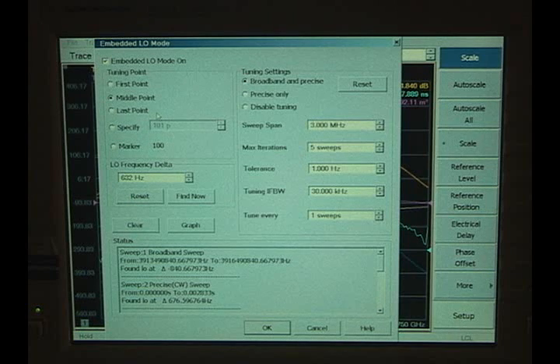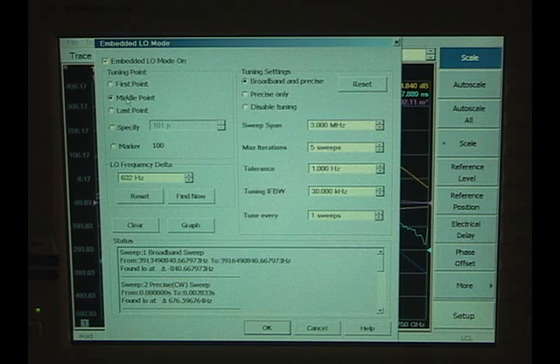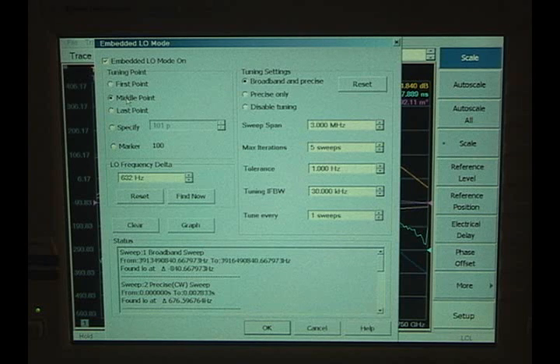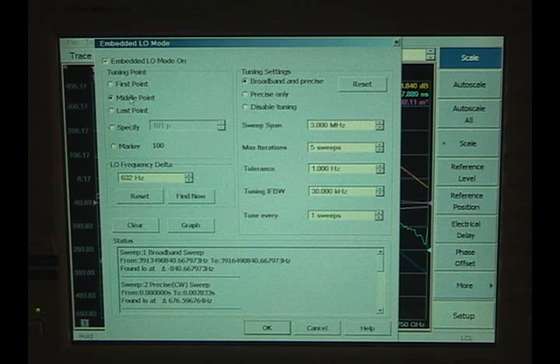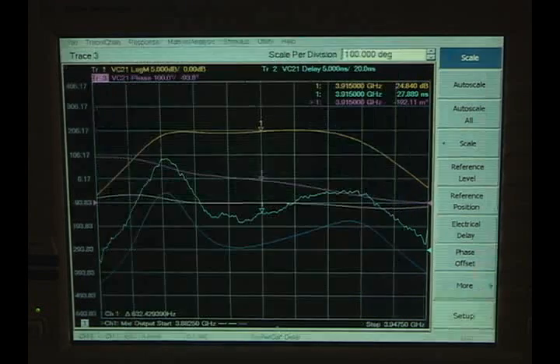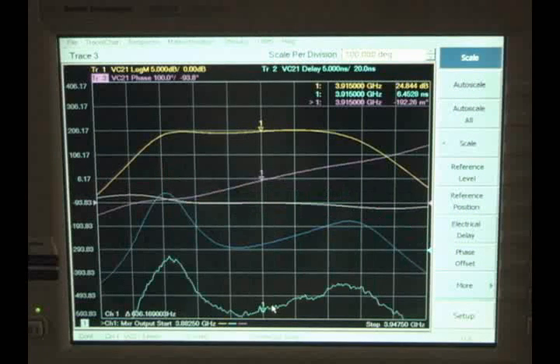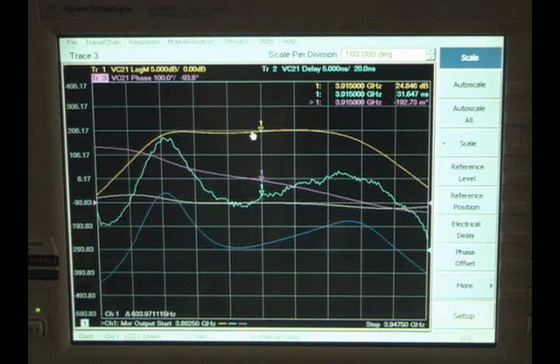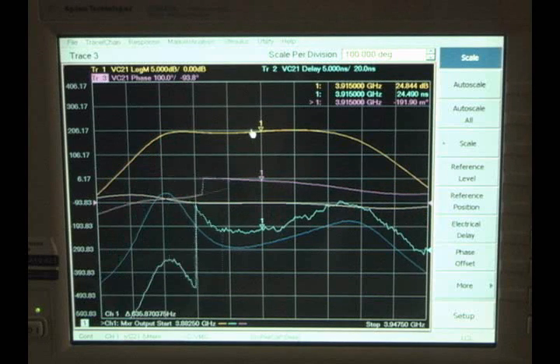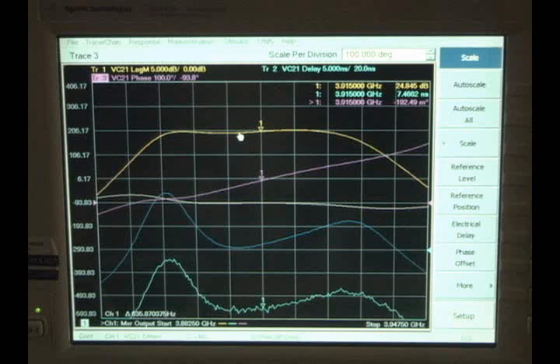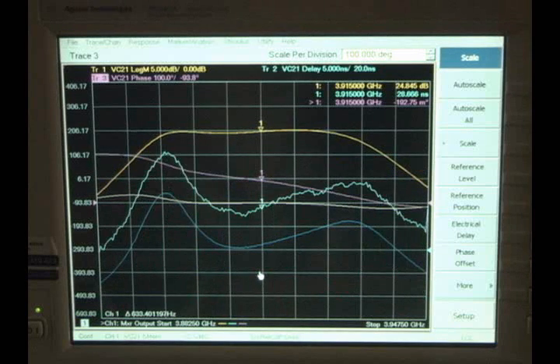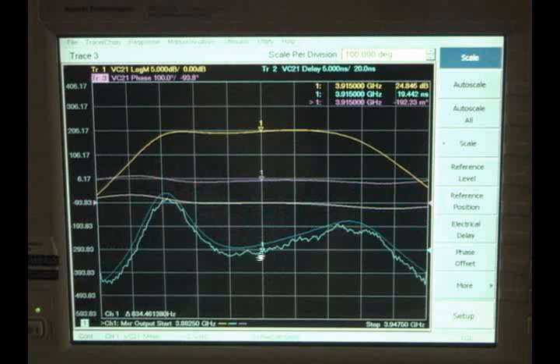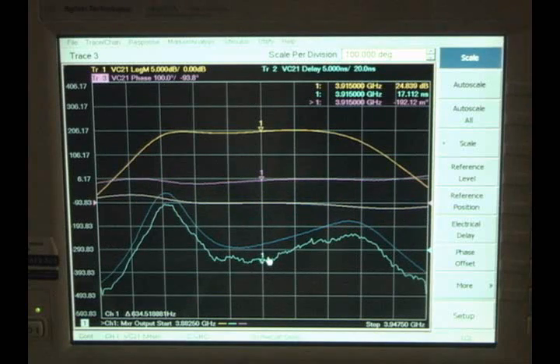In addition, in order to stabilize the phase, we're going to normalize an arbitrary point of the phase trace to the same position on the screen all the time. And that will remove the sweep-to-sweep phase variation that we get. And in this case, we're going to just normalize the middle point on the screen. So we click OK, and we notice a few things. Notice that our amplitude trace now has returned to the position it's supposed to be in. It lines up exactly over the memory trace. We notice our group delay is still wiggling around. It is moving about the correct value, but it's going above and below.